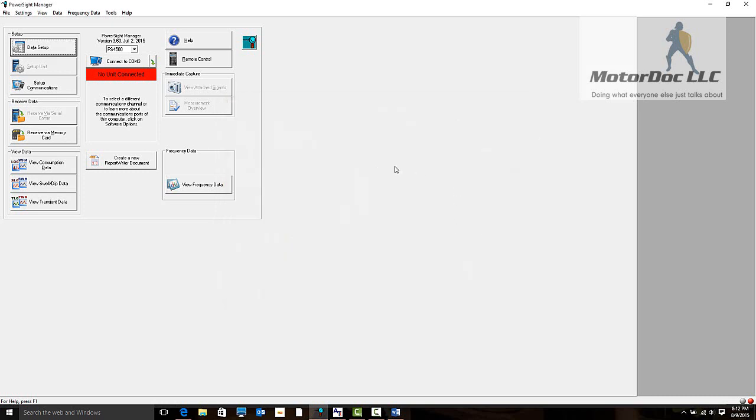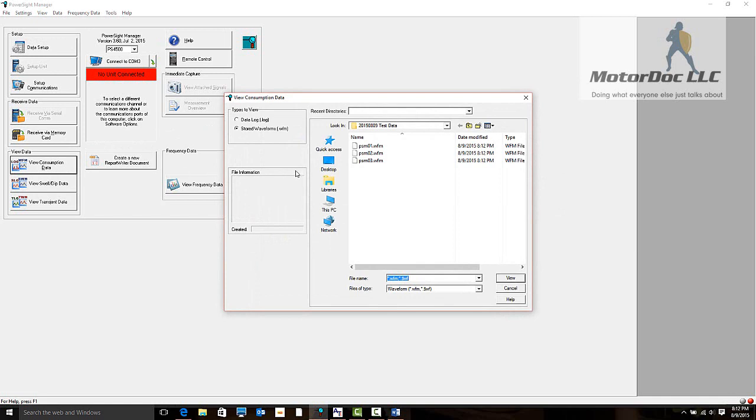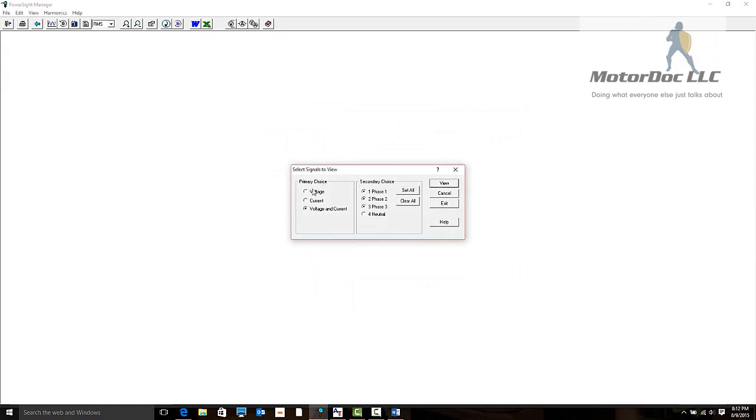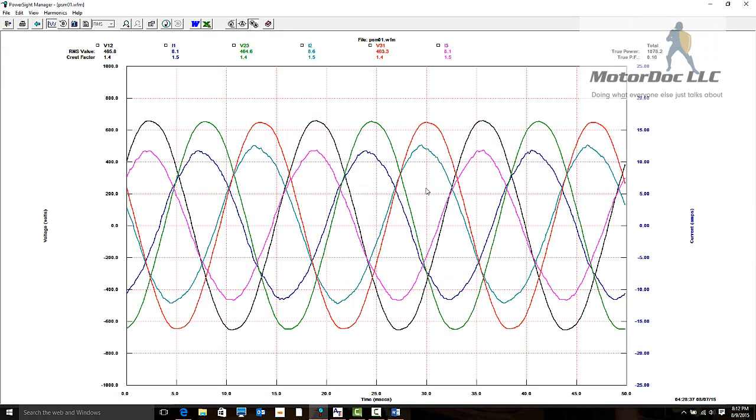Some of the things we can do from here is take a look at some of the information taken while we were taking our data. Let's go into our test data area. We have data log and stored waveform. Let's take a look at the waveform. This would be unloaded, 50% load, and full load on this particular machine. We're going to take a look at our voltage and current, the three phases, and let's view it. Here are our three phases of power on top of each other.